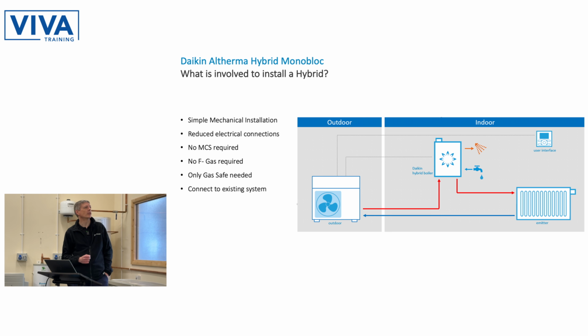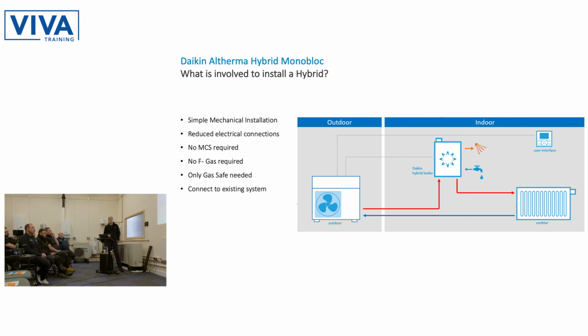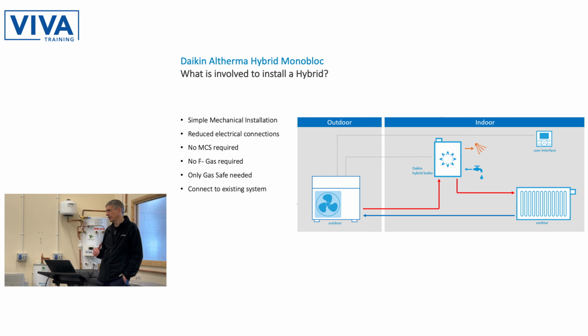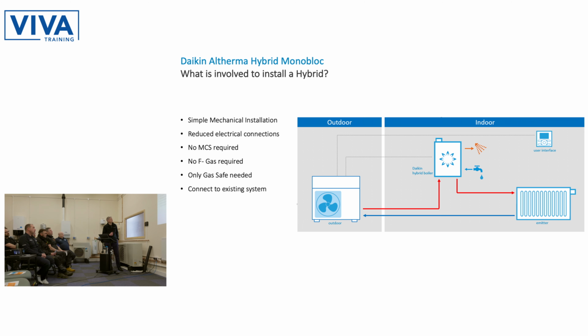So the mechanical installation is quite straightforward. There's not a lot of electrical connections. You don't need to be MCS certified to install one of these. Sorry? Because it doesn't qualify for the boiler upgrade scheme funding. So in order to access that, you'd need to be MCS or under an MCS umbrella scheme, but this is outside the scope of that. You don't need to be F-gas, you just need to be Gas Safe. It can also connect into an existing system, which I think we've got a slide on as well, in terms of the heat pump could be added to an existing combi boiler system. But I'll cover the ins and outs of that in a minute.